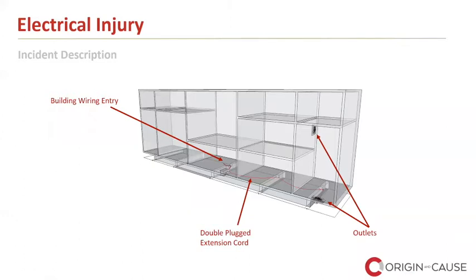There were also two duplex outlets mounted to the cabinet in a pretty rough install, one here and one up here. These appeared to be intended to power stereo equipment, but the way this was built, there was no legitimate way to power them. It is possible to power them with a double plugged cord though. Basically, if you plug an energized cord into one outlet on a duplex receptacle, the other outlet will become energized, allowing you to use that one normally.